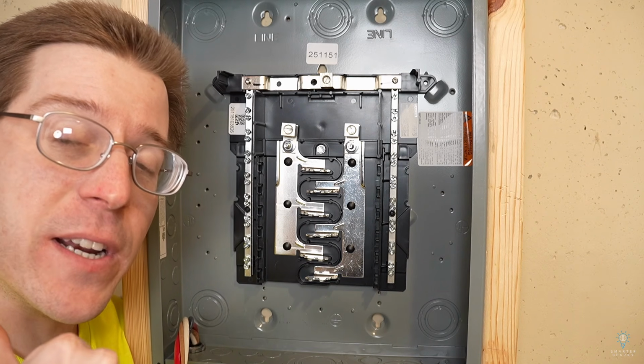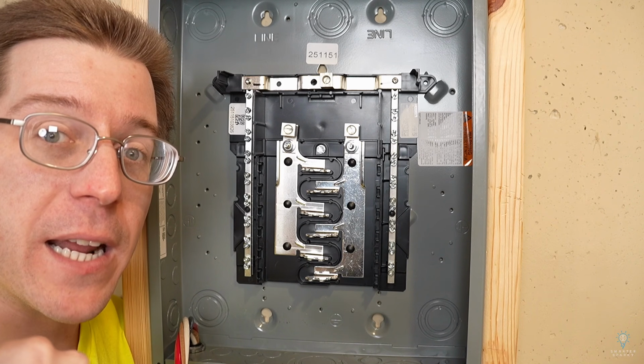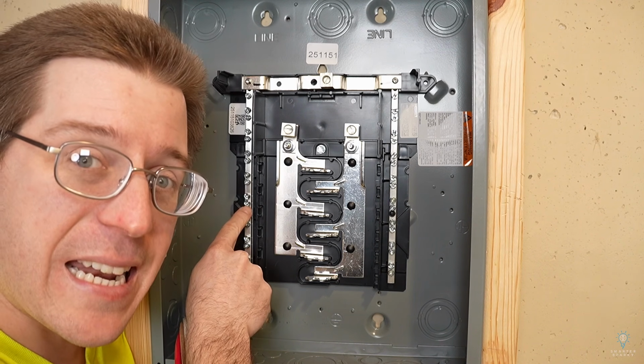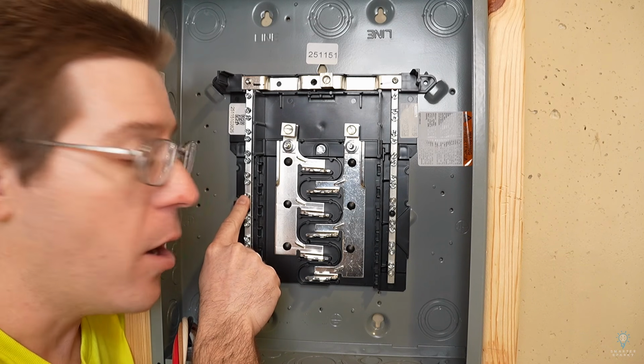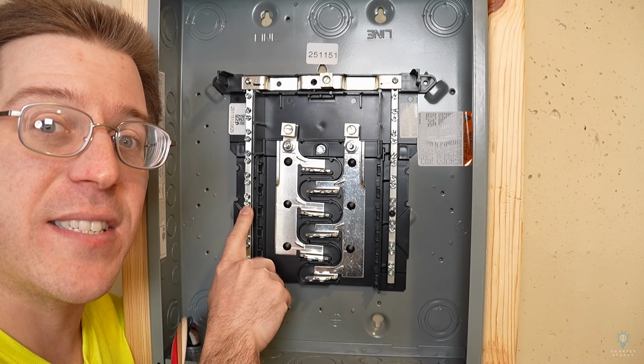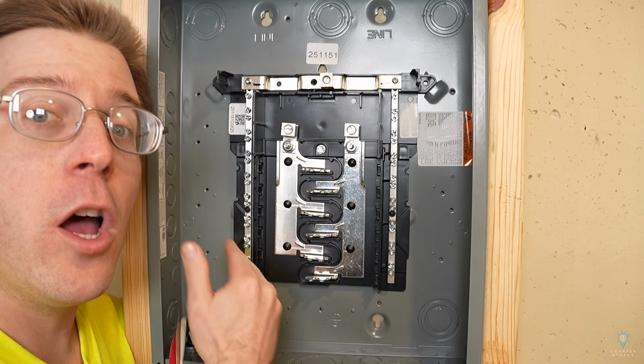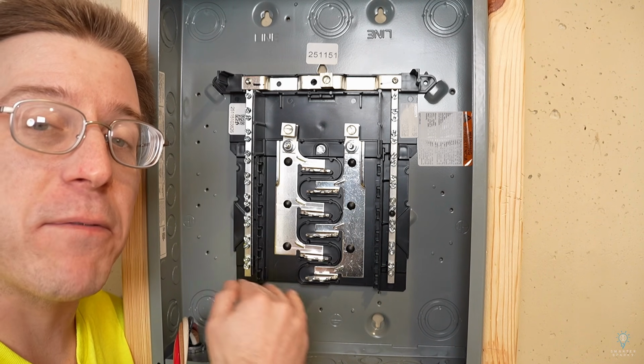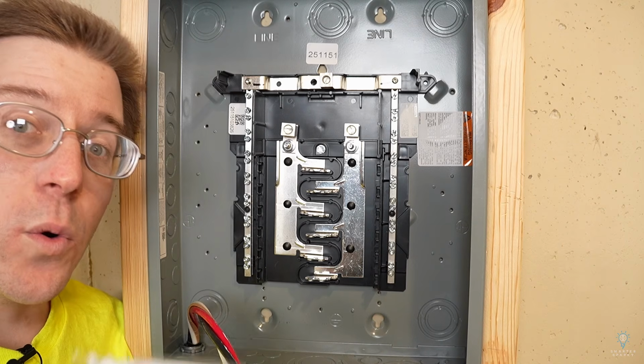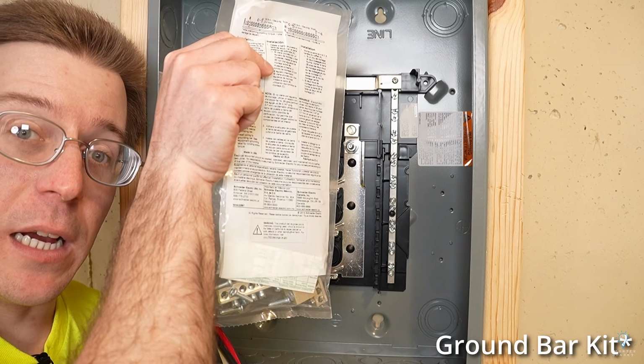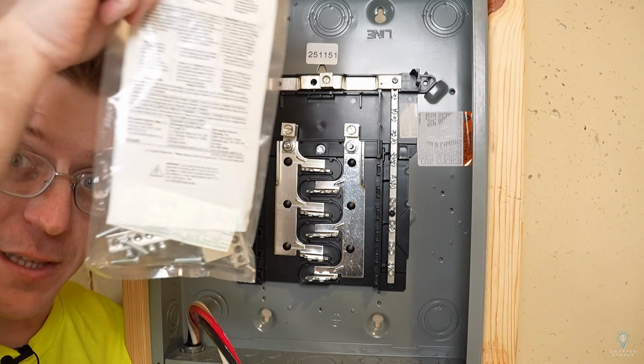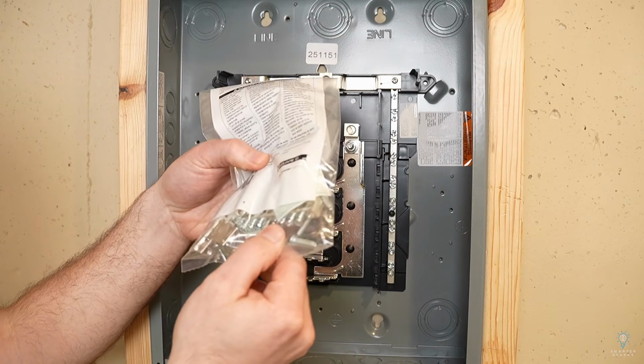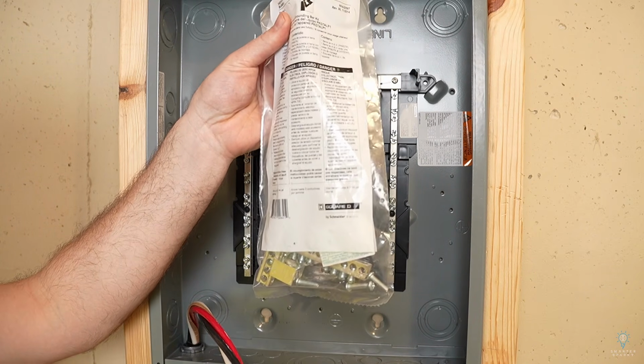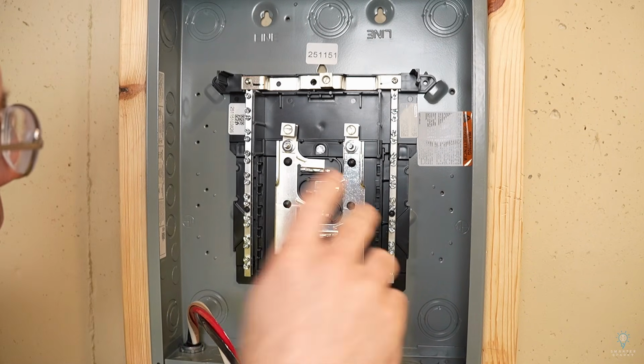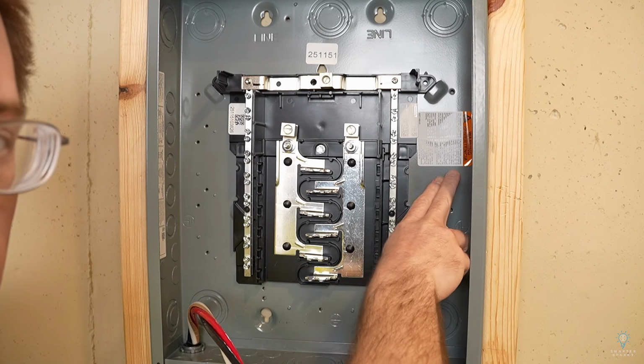Now, in that last video we saw in the main electrical panel, we could land our grounds and our neutrals on the neutral bar. We absolutely cannot do that in a sub panel. In a sub panel, grounds and neutrals have to be completely separate. So we need to install a ground lug kit. This panel actually came with this kit, and if we look in there, there's actually two ground bars in there, which is kind of cool that they send you two. I'm assuming they send you one for over here and one for over here.